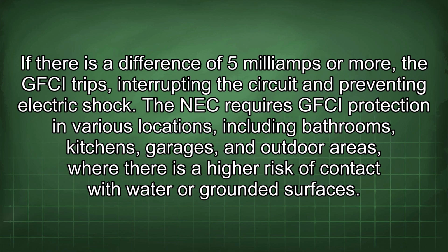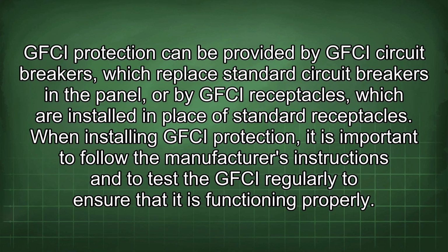The NEC requires GFCI protection in various locations, including bathrooms, kitchens, garages, and outdoor areas, where there is a higher risk of contact with water or grounded surfaces. GFCI protection can be provided by GFCI circuit breakers, which replace standard circuit breakers in the panel, or by GFCI receptacles, which are installed in place of standard receptacles. When installing GFCI protection, it is important to follow the manufacturer's instructions and to test the GFCI regularly to ensure that it is functioning properly.